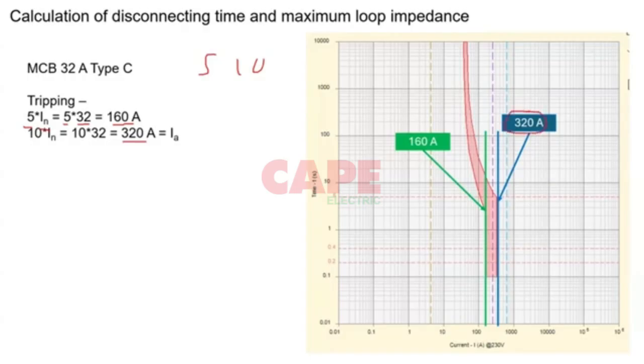You are not supposed to take 160 amps, because you are not sure whether the actual fault is going to come at 160 amps. If it is less than that, then it is not going to trip. So if you take the higher value, then even if there is a variation of 5 to 10 percent, or 20 or 30 percent, this protective device will trip. So you are supposed to take the higher value. So you are taking 320 amps as the tripping characteristic.